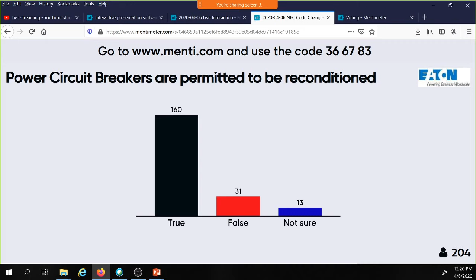Molded-case circuit breakers are permitted to be reconditioned - the answer to that is false. We cannot take a molded-case circuit breaker, take it apart, and recondition it. This version of the NEC has added some clarity on that, and I'll help you understand it. Molded-case circuit breakers are devices that NEMA and others, and now the NEC, recognize you really don't want to be taking apart. There are some things you can do to make sure a breaker is functioning correctly, and you can do some testing on that.